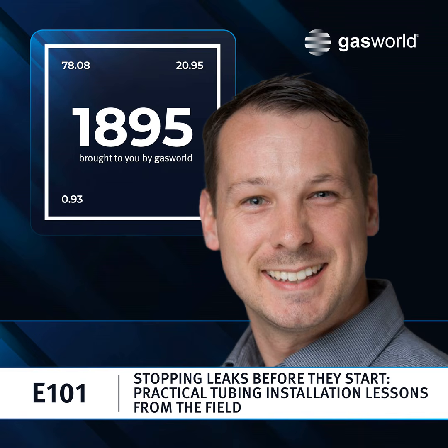As long as you don't have progression beyond the useful life of the fitting, then there's no issue retightening that fitting up, following the manufacturer's installation. Again, it may be a little bit different than the initial installation, but just making sure you're following those directions and then fitting it back up. You did mention how do we know when we need to swap out fittings? That visual inspection is always key.